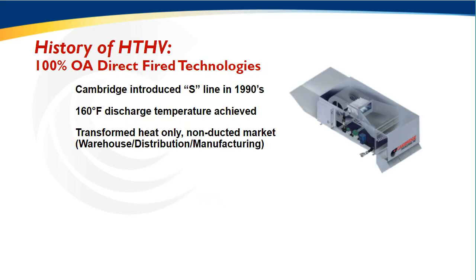So again, for a little bit of a history lesson, this technology and the concept of heating buildings with outside air is not new. It has been around for some time. It really stems back to the mid-90s, where Cambridge introduced the blow-through high-temperature heat ventilation system for design-build and new construction mechanical contractors. What they saw is these large open spaces were primarily being heated, and still to this day, with unit heaters or smaller terminal heating systems strung along the perimeter of a building with large gas connections, many pieces of equipment, many electrical connections, and really no ventilation systems.